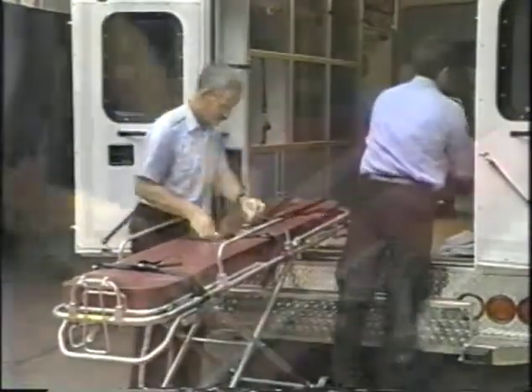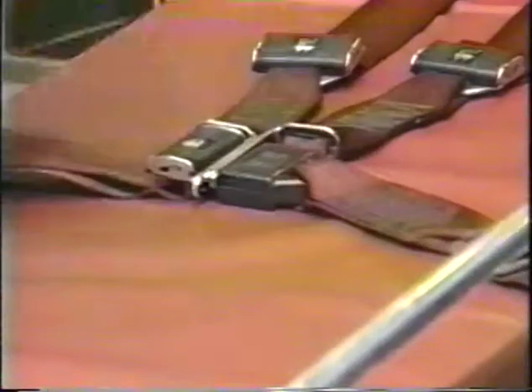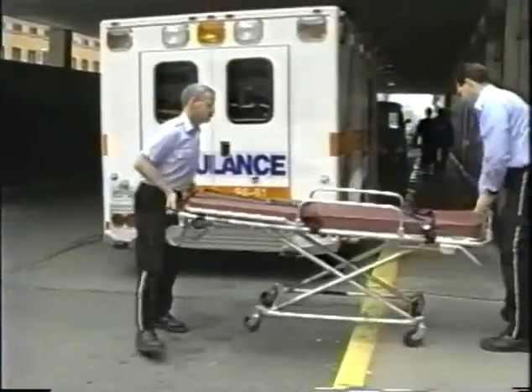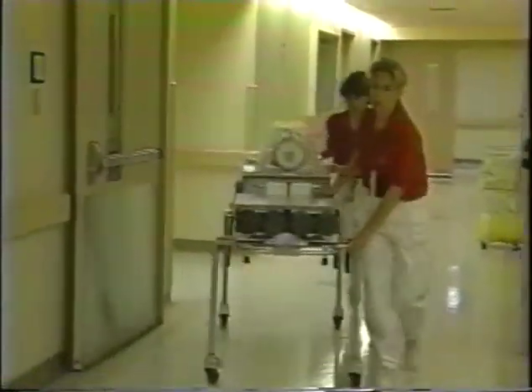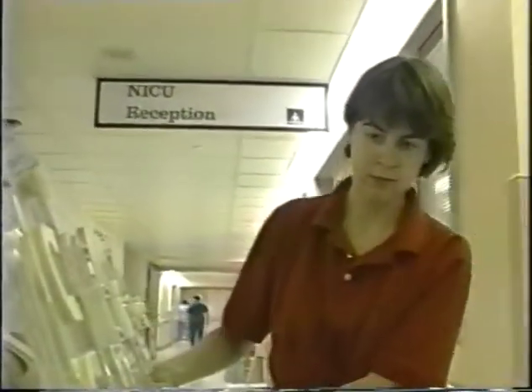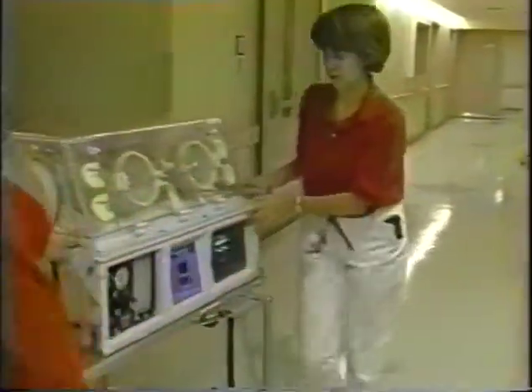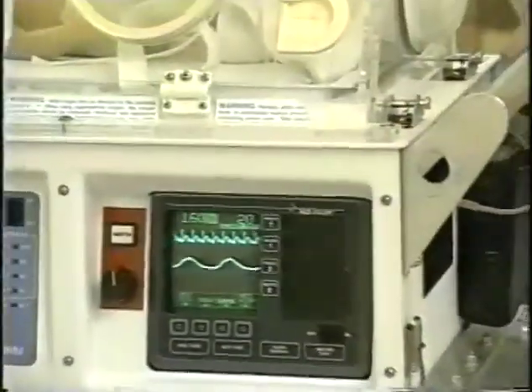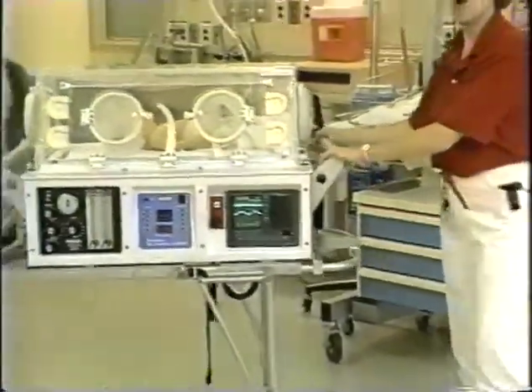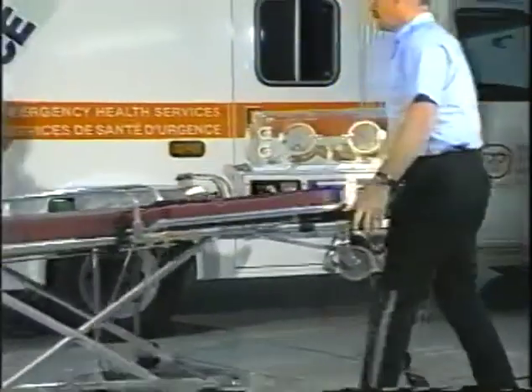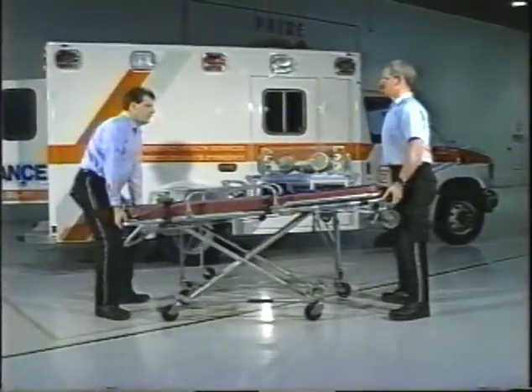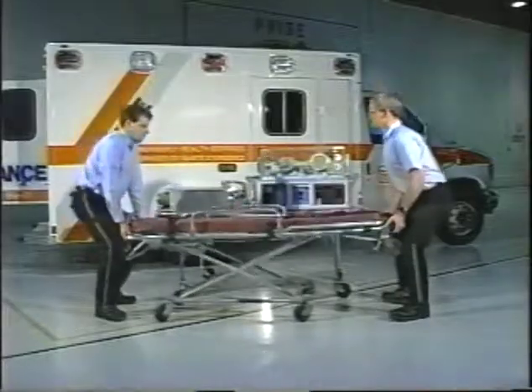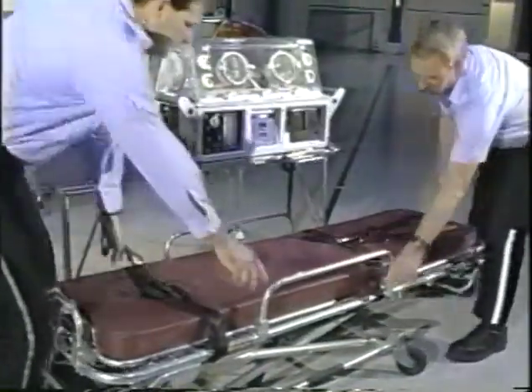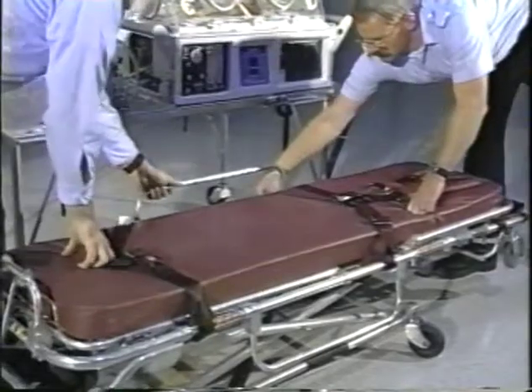Keep the stretcher straps secured across the mattress and ensure there are no loose straps hanging over the side of the stretcher. If space precludes moving the stretcher into the nursery, the incubator deck may be wheeled out into a more spacious transfer area. Avoid transferring the incubator deck in a cold environment in order to protect the neonate from any unnecessary heat loss. Set the 35A stretcher height at one level lower than the incubator adapter deck height and lower the side rails. Wheel the 35A load assist stretcher under the deck from either end.